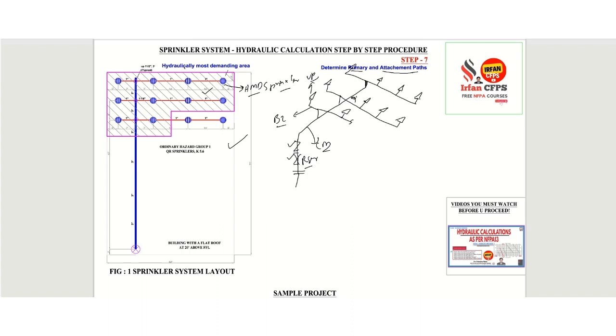Now what we need to do is determine the primary path and the attachment paths. First of all, the hydraulically most demanding sprinkler is this one. So now I will define the primary path and attachment path definitions, then we will look into the noding. Primary path is the path that the water takes from the water supply to the remotest sprinkler or single most demanding sprinkler.